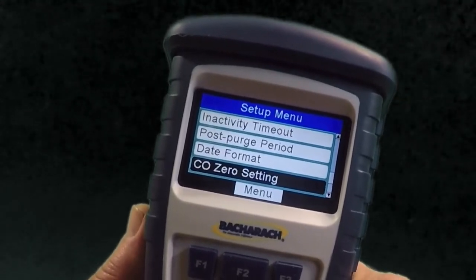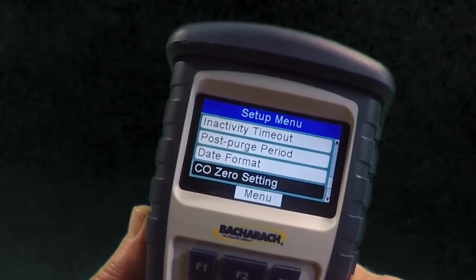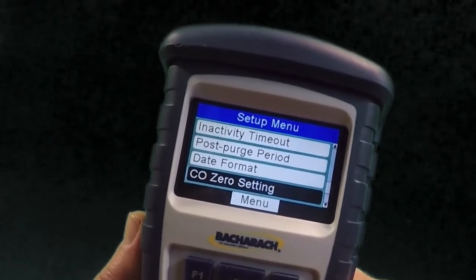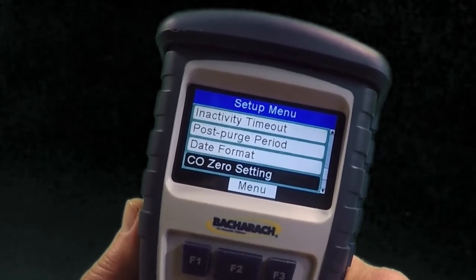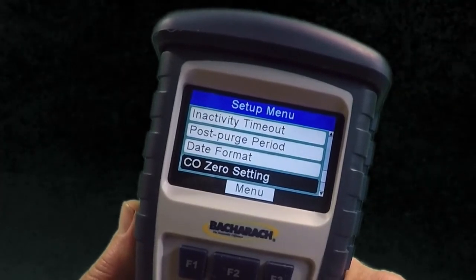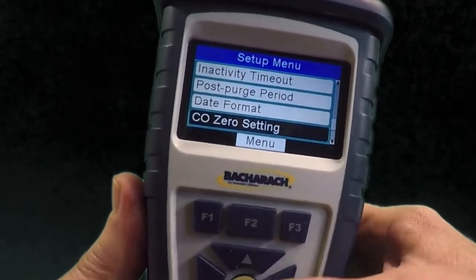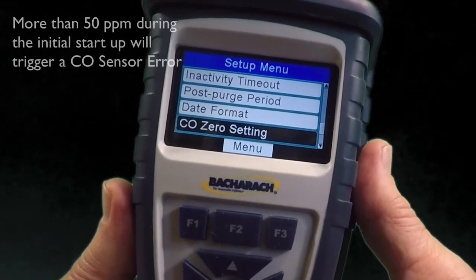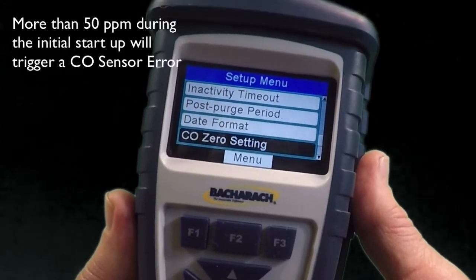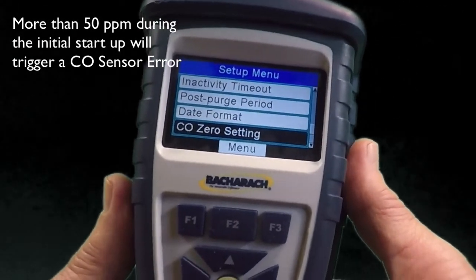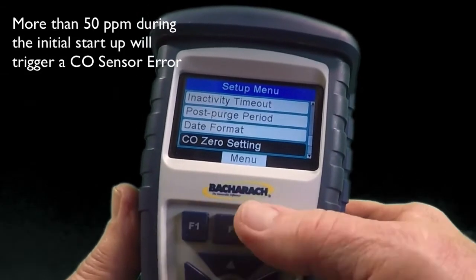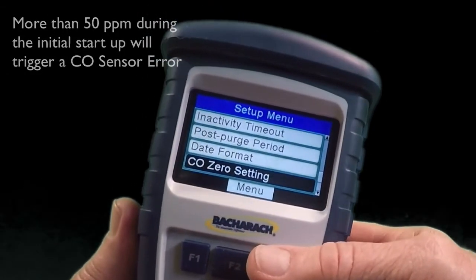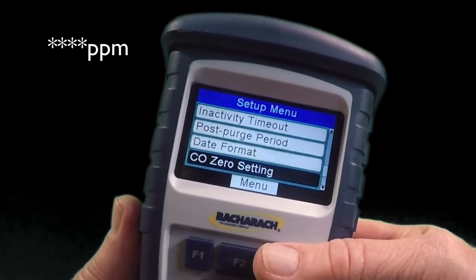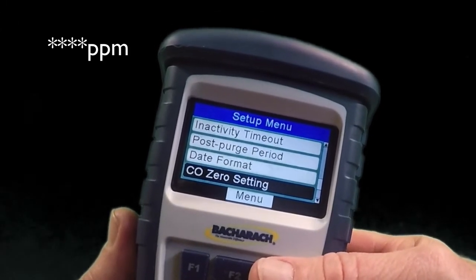If the instrument is set up for a manual 0, on the other hand, the CO levels will be accurately displayed after the warm-up period. As mentioned previously, if the instrument is set up for an auto 0 and there's more than 50 ppm in the space, the instrument will display a CO error message, and there will be several asterisks in the display before ppm.